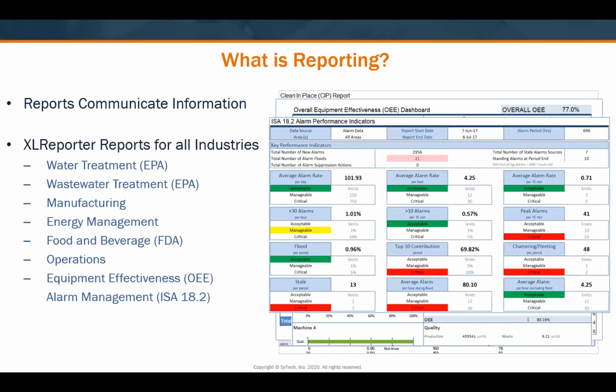Alarm management. You're creating all these alarms in the VT SCADA, and now you want to know information so you can prevent the operator from unnecessary interruption. In fact, beyond that, complacency—you have an alarm that just repeats itself, it chatters, and the operator's going to get very complacent. They just hit okay. You ask the operator what's all that about, and they say, I have no idea, I just hit okay. That's not a good situation. ISA recognized it's not a good situation, so they came out with ISA 18.2, or IEC 62682 if you're in Europe.